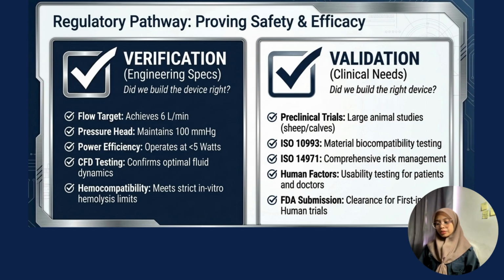Human factors are also one of the points in validation, where usability testing ensures that patients, caregivers, and clinicians can safely operate the controller, alarms, and battery system. Last but not least, finally, all safety data and preclinical results are submitted to the FDA before approval for first-in-human clinical trials can be granted. In conclusion, verification confirms that the device meets engineering requirements, while validation confirms that the device safely fulfills clinical needs before human implantation.